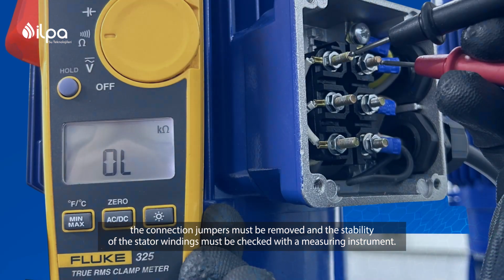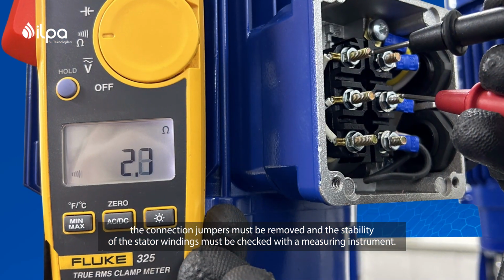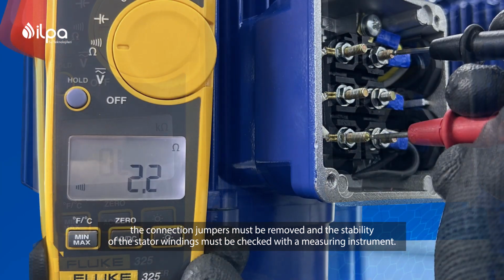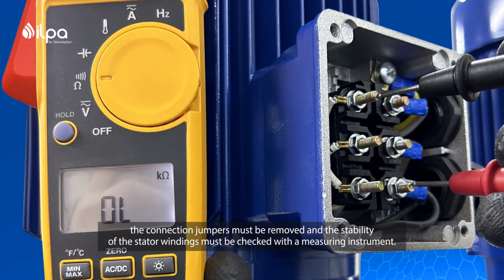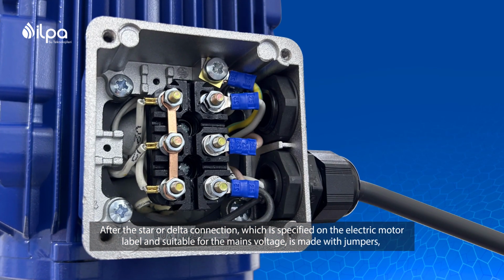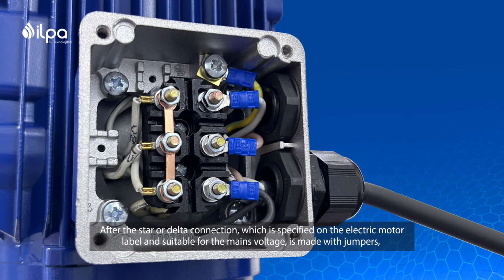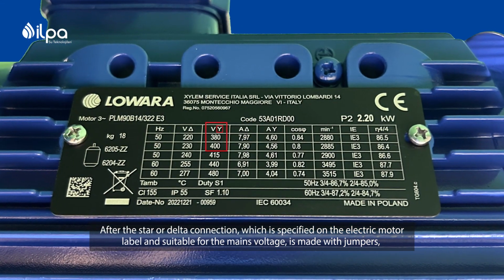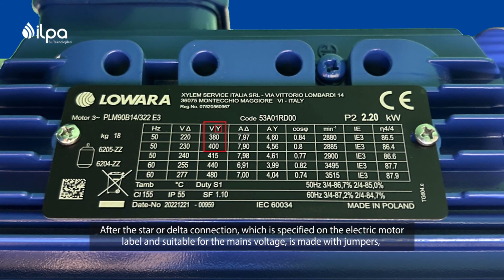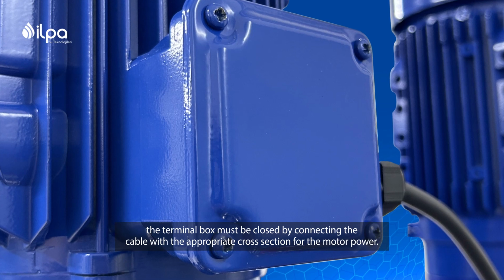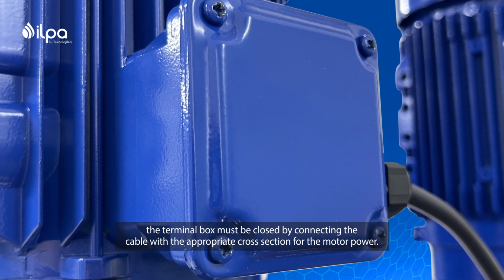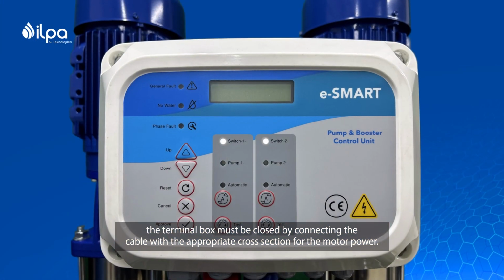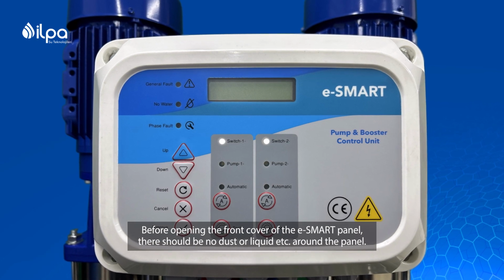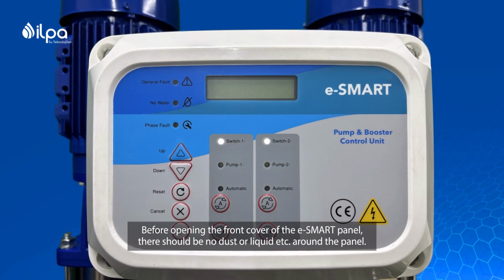be opened. The connection jumpers must be removed and the stability of the stator windings must be checked with a measuring instrument. After the star or delta connection, which is specified on the electric motor label and suitable for the mains voltage, is made with jumpers, the terminal box must be closed by connecting the cable with the appropriate cross-section for the motor power.